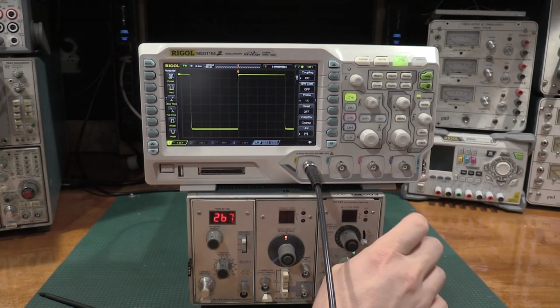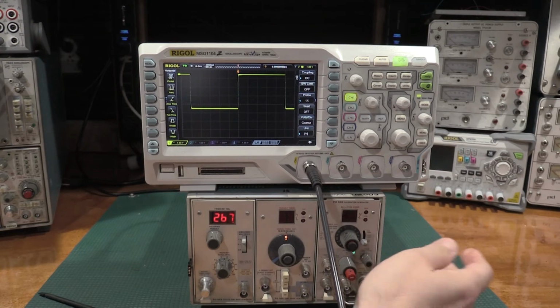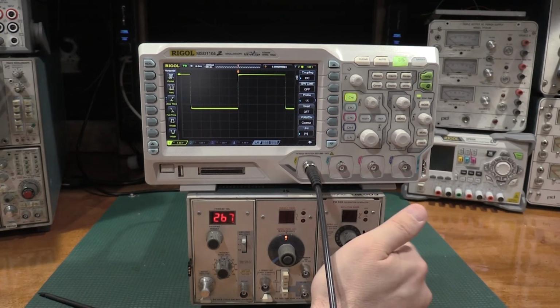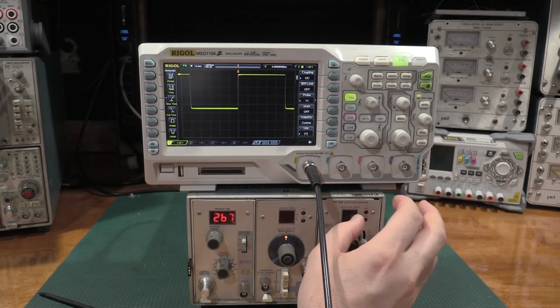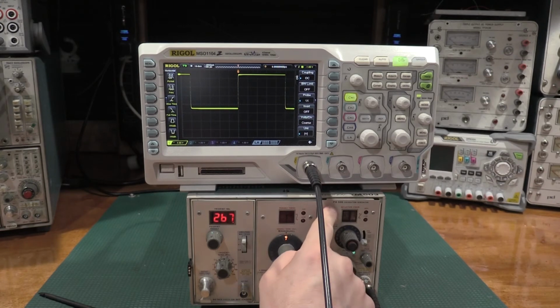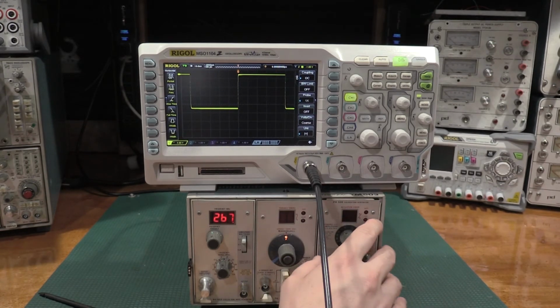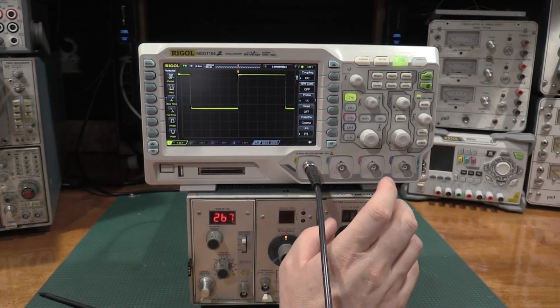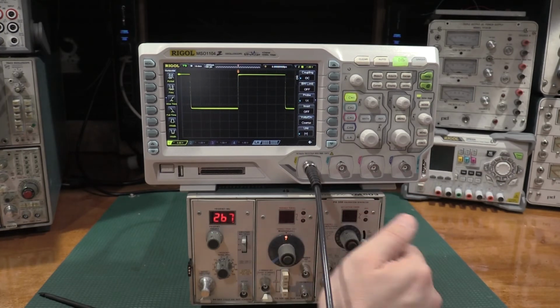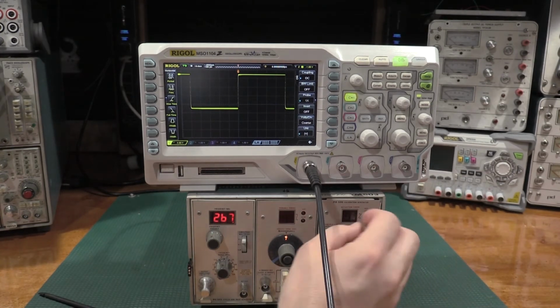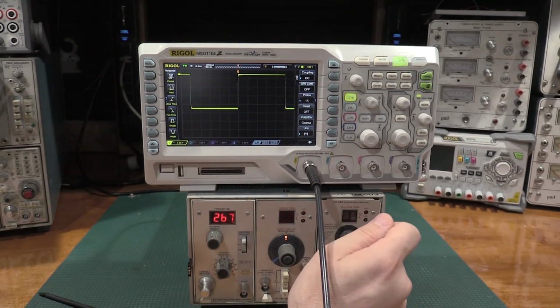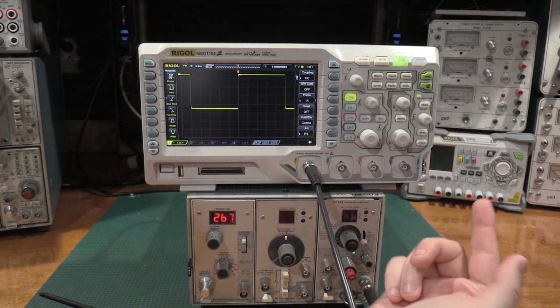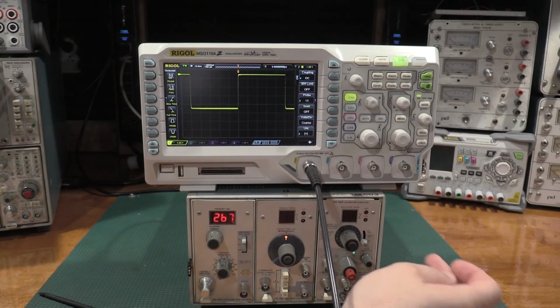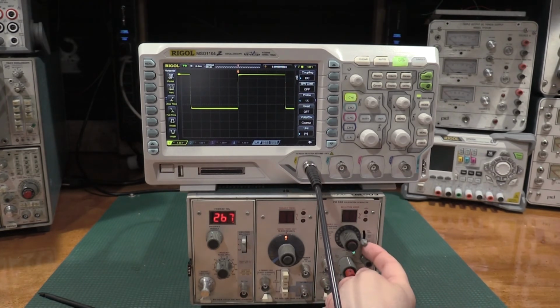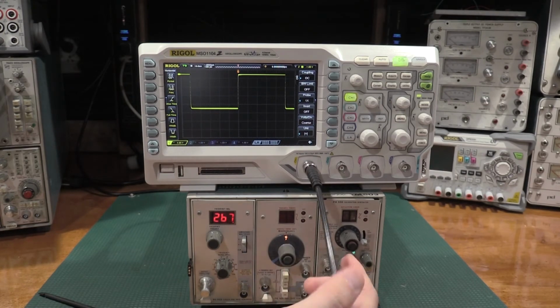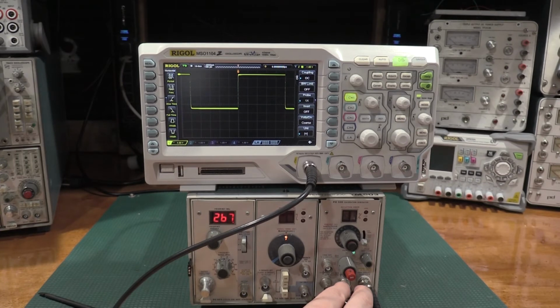This is just, so the high amplitude is just an adjustable square wave. That's all it is. Same thing that's in the Type 106. Sometimes I'll switch to my Type 106 from the PG506. The reason for it is this is not a PG506A. This is just a PG506. So this guy tops out at about 64 volts peak to peak. The PG506A completely replaces the 106, goes to a 100-volt square wave, so it'll drive the tunnel diodes and things like that. My particular PG506 does not have enough horsepower to drive my calibration fixture, so I need the larger waveform on the 106. So this high amplitude setting is exactly the same as a 506, along with the fast rise, fast fall outputs on the 506, or on the 106.